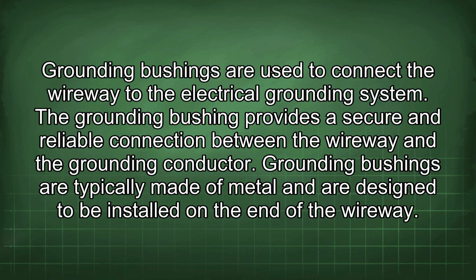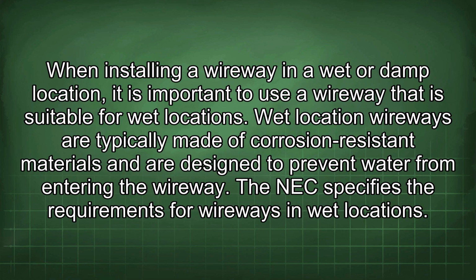Grounding bushings are used to connect the wireway to the electrical grounding system. The grounding bushing provides a secure and reliable connection between the wireway and the grounding conductor. Grounding bushings are typically made of metal and are designed to be installed on the end of the wireway. When installing a wireway in a wet or damp location, it is important to use a wireway that is suitable for wet locations. Wet location wireways are typically made of corrosion-resistant materials and are designed to prevent water from entering the wireway. The NEC specifies the requirements for wireways in wet locations.